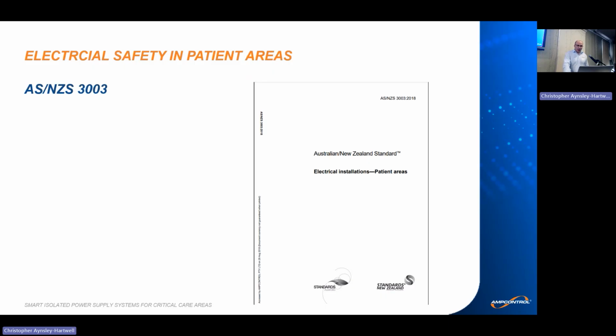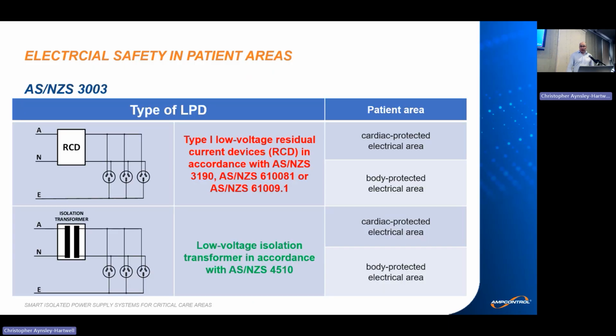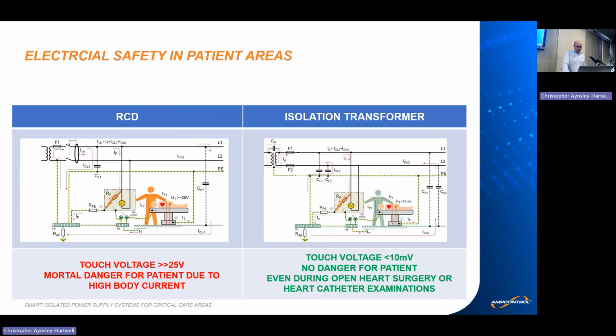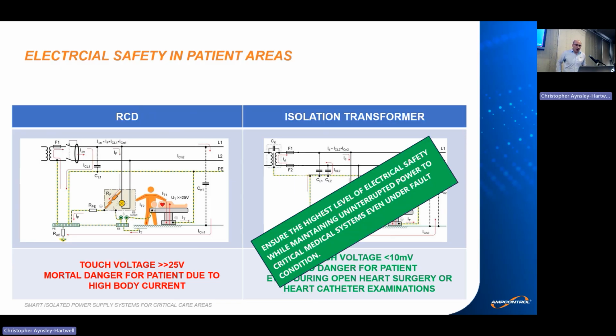As we know, the AS 3003 standard specifies requirements for electrical installations in patient areas. The standard mandates the use of leakage protective devices in cardiac protected and body protected electrical areas, and recognizes two types: residual current detection device type 1 and low voltage isolation transformer. I hope we can all agree that between these two solutions, only the isolation transformer can provide the highest level of electrical safety while maintaining power availability for critical medical systems under fault condition. If some of you have a different view, we have a separate presentation explaining the difference between these two approaches.